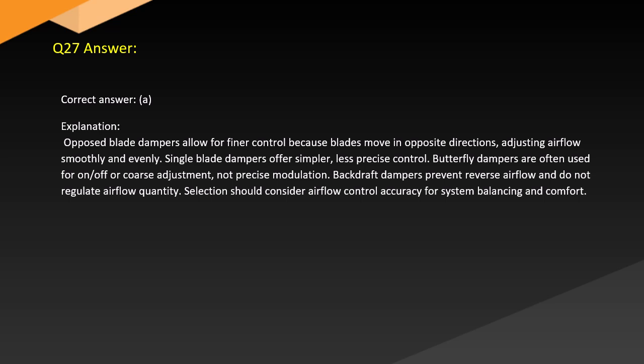Answer. Correct answer: A. Explanation. Opposed blade dampers allow for finer control because blades move in opposite directions, adjusting airflow smoothly and evenly. Single blade dampers offer simpler, less precise control. Butterfly dampers are often used for on-off or coarse adjustment, not precise modulation. Backdraft dampers prevent reverse airflow and do not regulate airflow quantity. Selection should consider airflow control, accuracy for system balancing, and comfort.